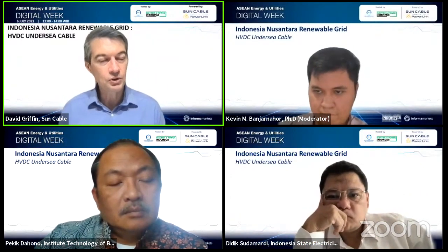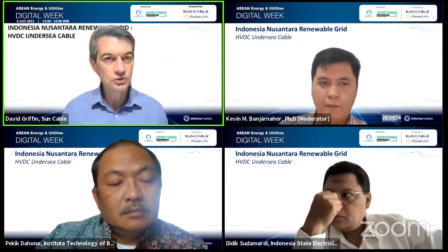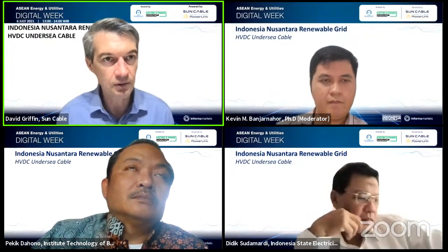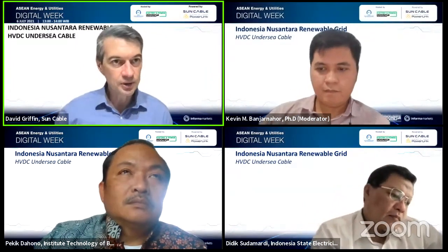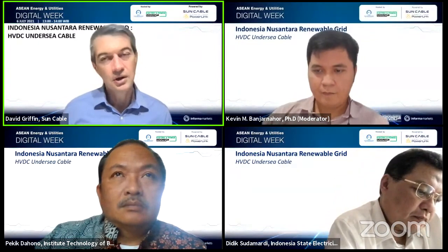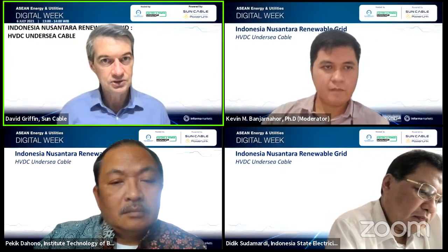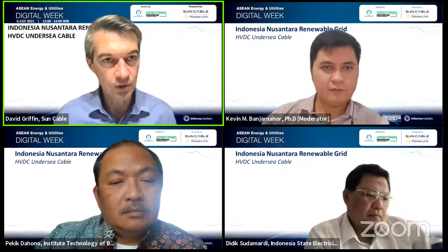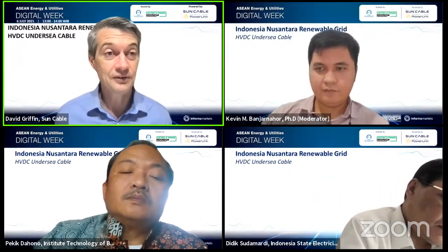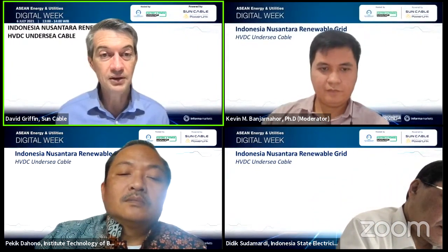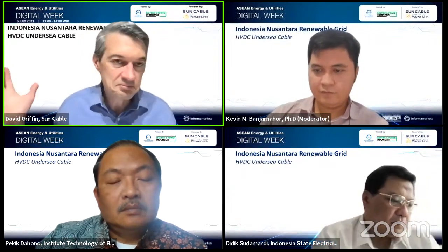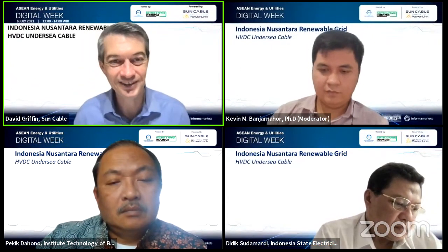And part of the reason for that is because during the day, we use what would be a massive amount of spill, because we can't transmit it, to charge the batteries. And then we discharge the batteries in the late evening and through the night. So if we were to measure the capacity factor, and I don't know what the capacity factor is because we measure what matters, and capacity factor does not matter. But if I was to measure it, it's probably in the order of 70 or 80% capacity factor as a system. The capacity factor of the solar farm is, who cares? It's not a pertinent number.